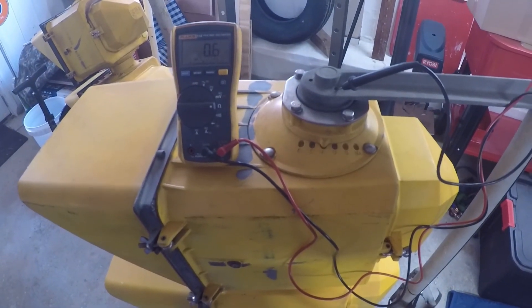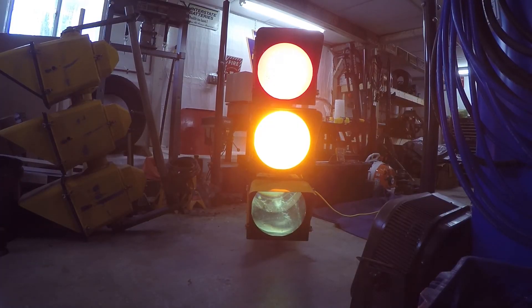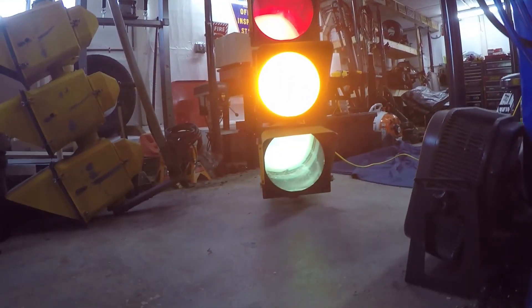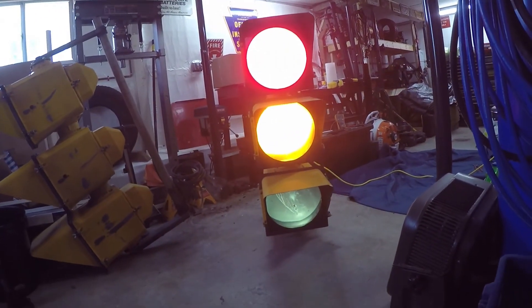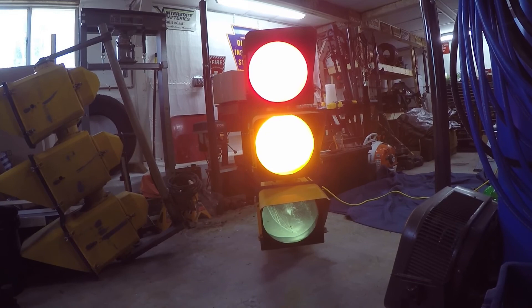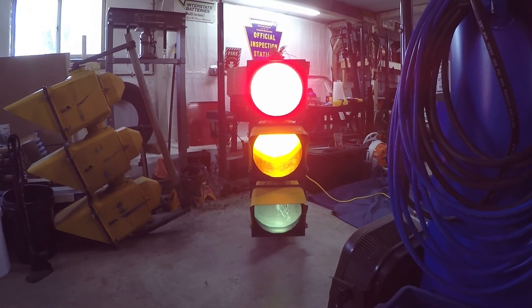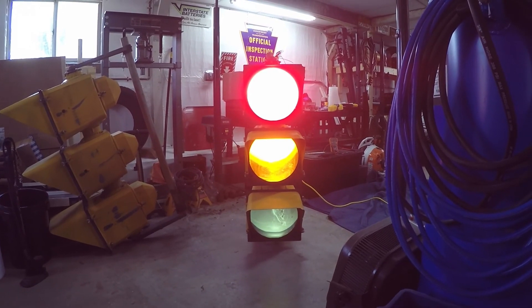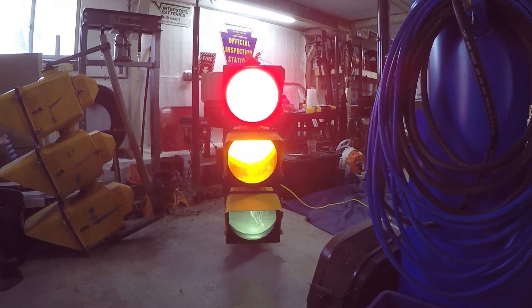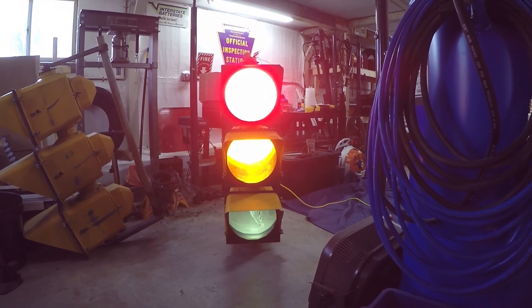I think we're ready to plug it in. It looks like it's working pretty well. I'm probably not going to do it on video but I'm going to check it again to make sure there's no voltage on the housing — but since we know that the grounding is good on there, I think if we had an issue with that still, we would have tripped a breaker. So everything looks like it's good to go. I think I'm going to move on now — the next video will probably be about either mounting or sequencing. So far this has been a pretty fun project. I hope you've enjoyed the videos, stay tuned for the next one, thanks for watching.